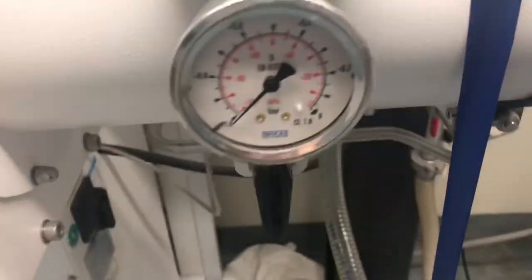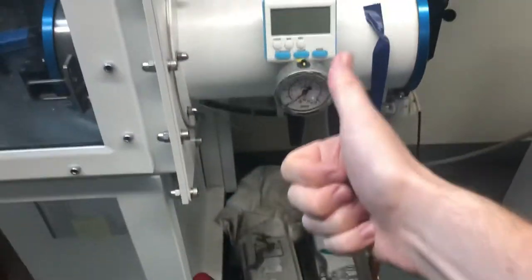So now that the pressure's all the way down to zero, I have it in the closed position. That means vacuum isn't pulling anymore. We can go ahead and turn this off. Vacuum pump off, pressure doesn't change. Give it a thumbs up. That's a good job.